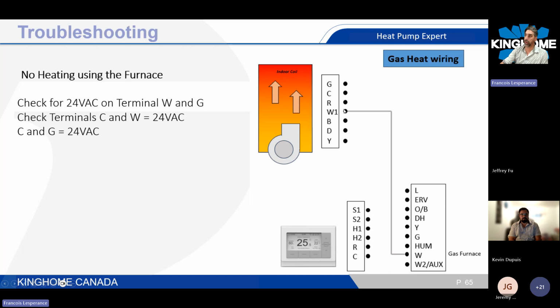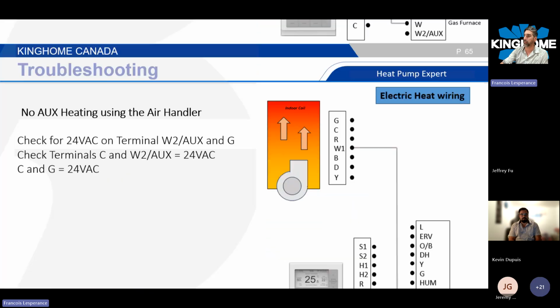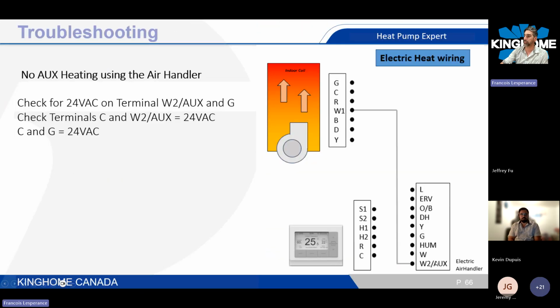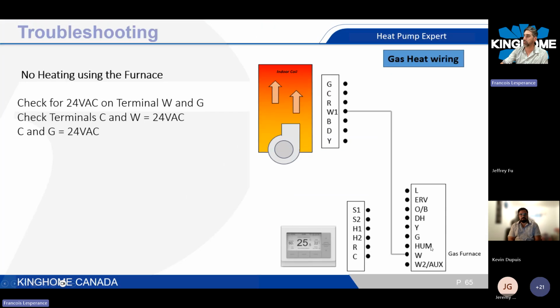If you don't, it's good to double check which terminal is in use inside this white thermostat, the master thermostat over here. If it's an air handler, you will use Aux to power up the air handler. If it's a gas furnace, you will use W to power up that gas furnace. So maybe there are wrong connections over here. This is the kind of stuff you need to check whenever you are troubleshooting.